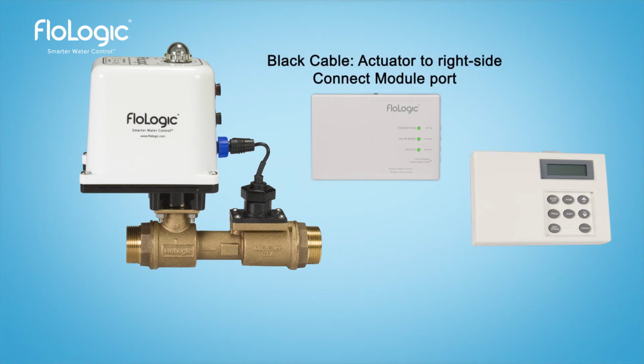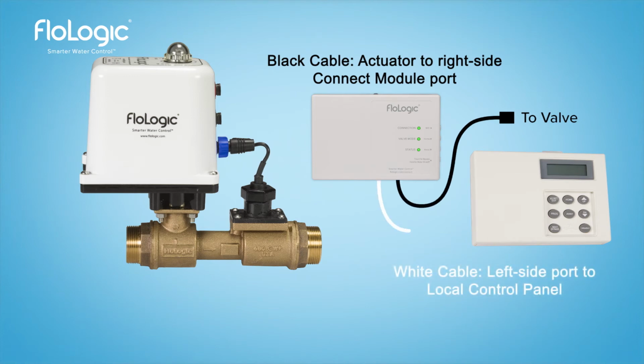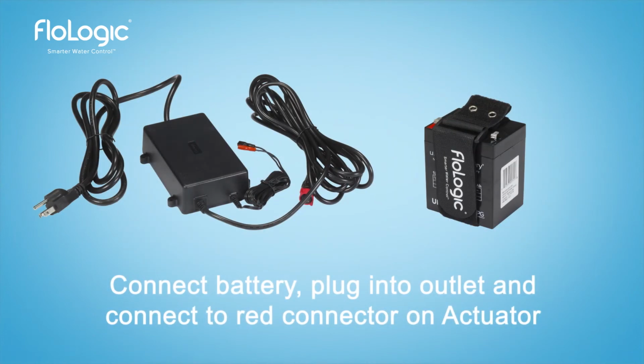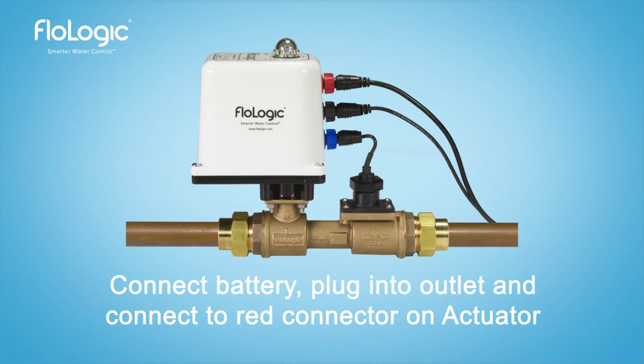Connect the communication cable to the black connector on the FloLogic actuator assembly. Connect the other end to the Connect Module on the right-hand port, then connect the local control panel from the left-hand port using the connector cable. Connect the battery to the power supply and plug it into a 120-volt outlet. Then connect the power cable to the red connector on the FloLogic actuator assembly. Upon powering up, the valve should auto-exercise.